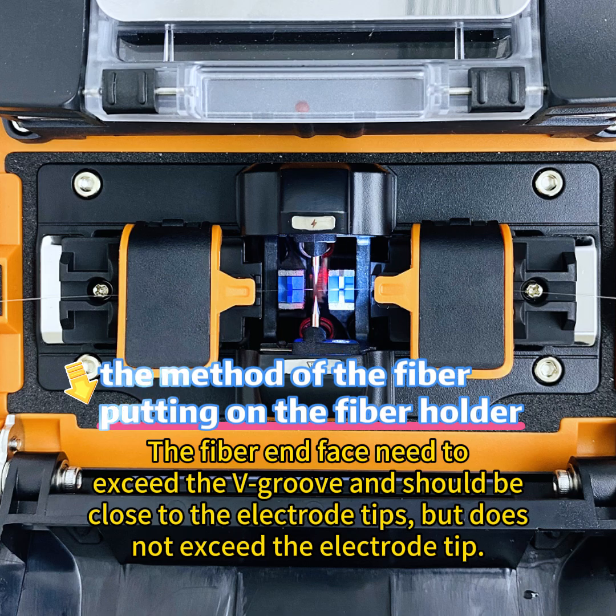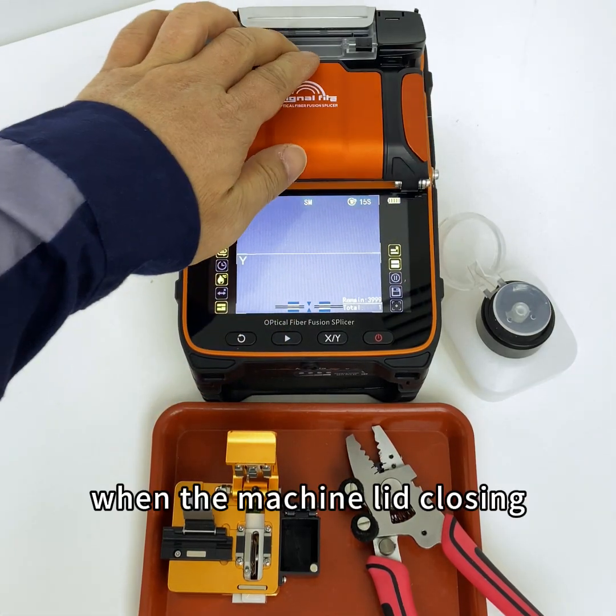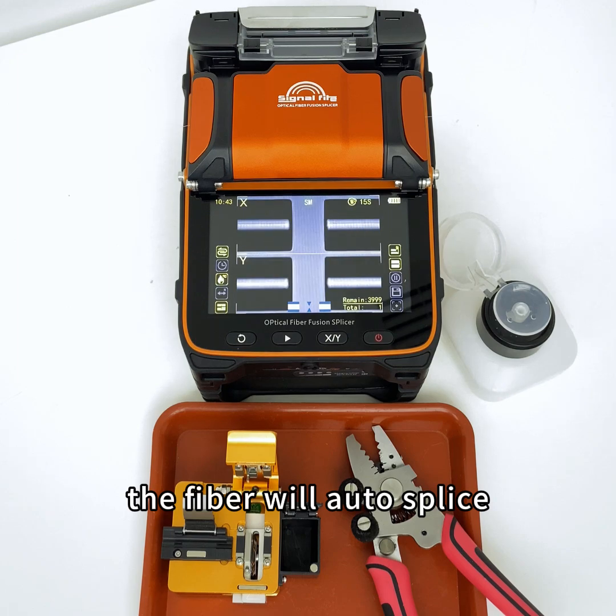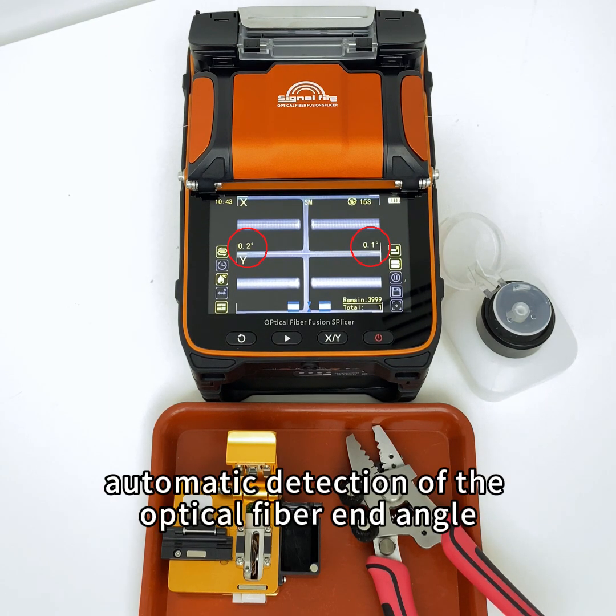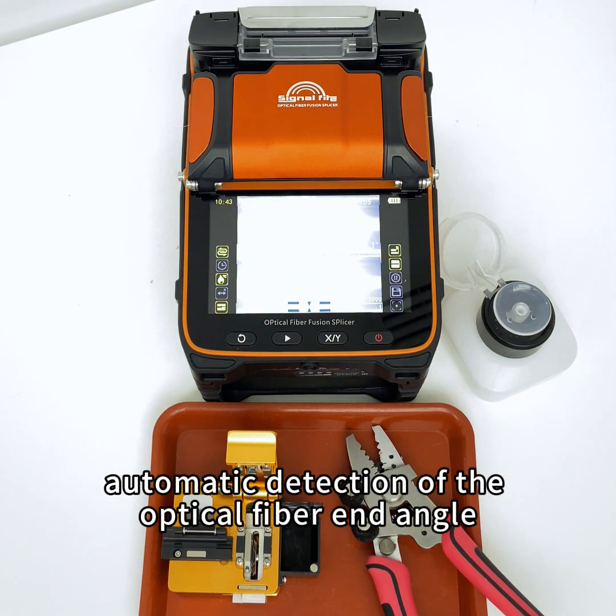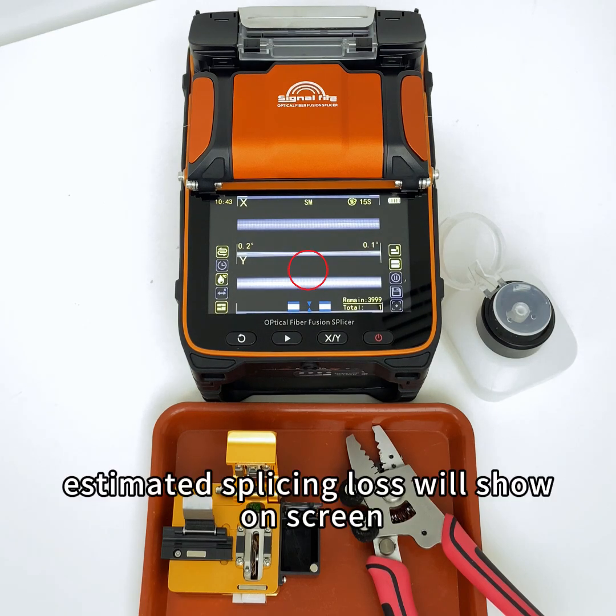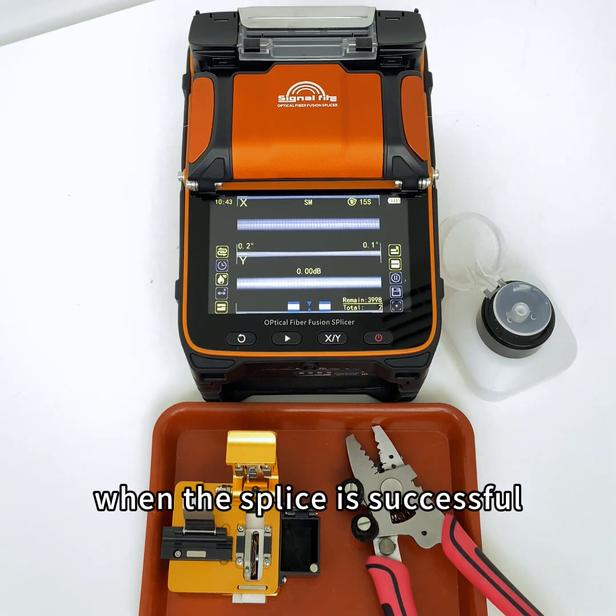The fiber end face needs to exceed the V-groove and should be close to the electrode tips, but not exceed the electrode tip. When the machine lid is closed, the fiber will auto-splice. Automatic detection of the optical fiber end angle. Estimated splicing loss will show on screen when the splice is successful.